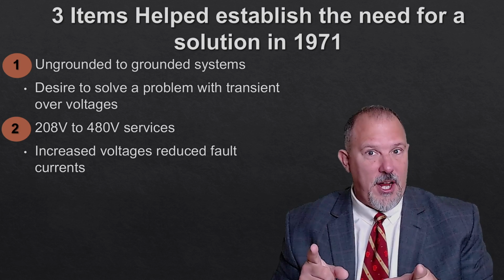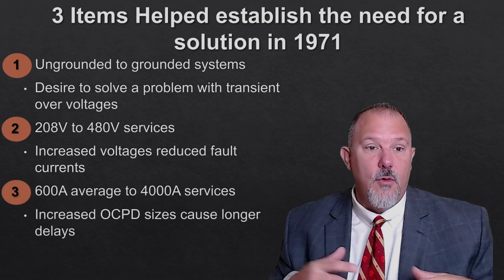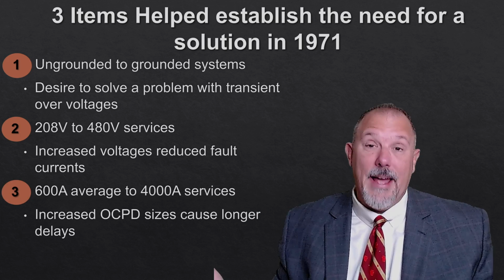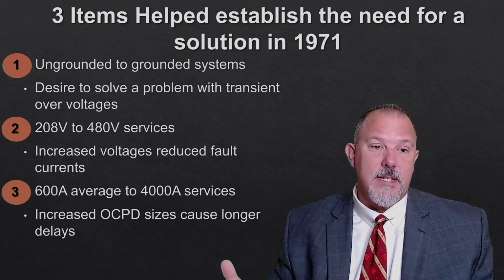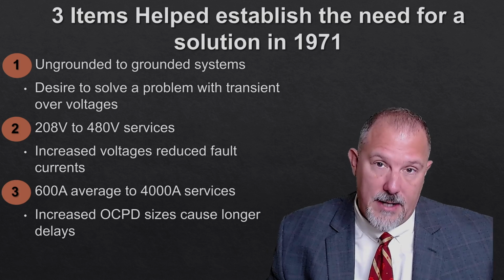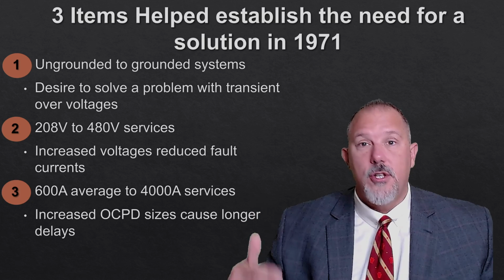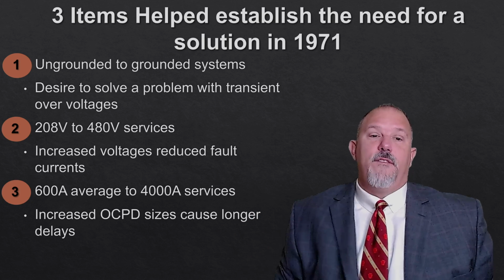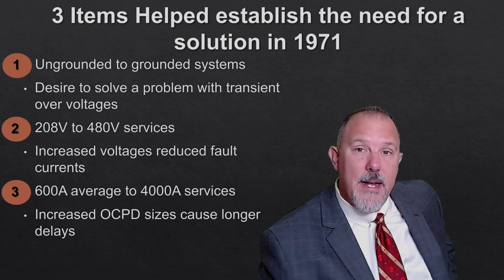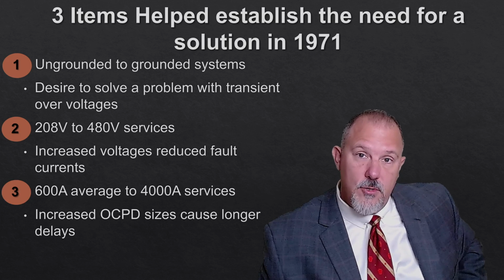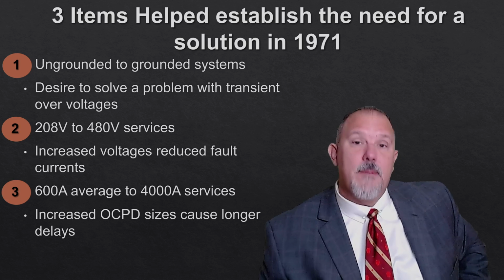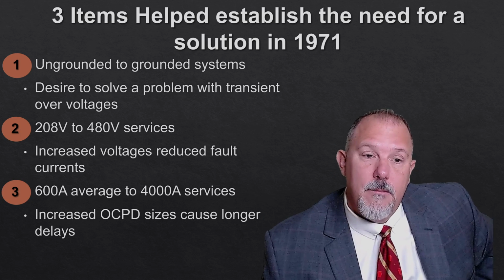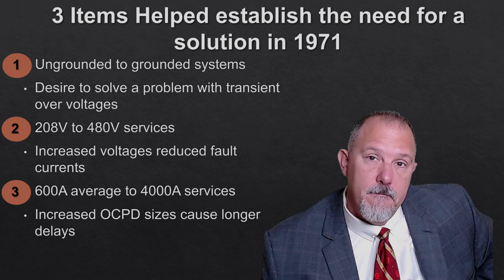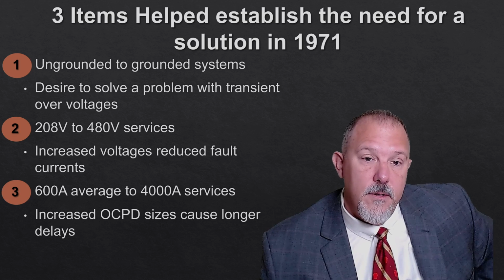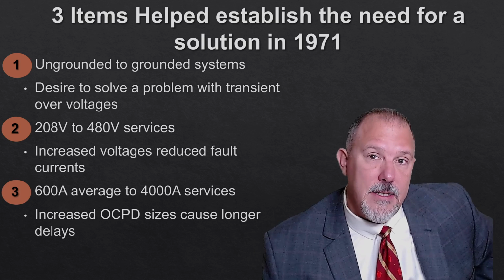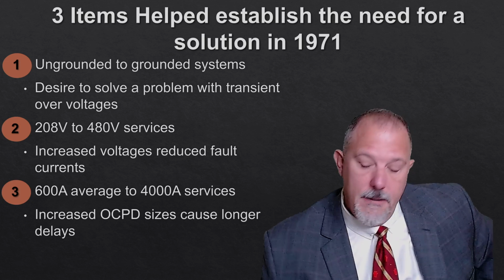But the third change is what really put everybody over the edge. They went from 600 amp services up to 4,000 amp services. So your service size increased. And what does that mean? If I go to a 4,000 amp service, that means my overcurrent protective devices are huge. The instantaneous pickup, which we're going to talk about, is way over to the right. My arcing currents may have gone up, but not enough in relationship to the instantaneous. So what was happening?